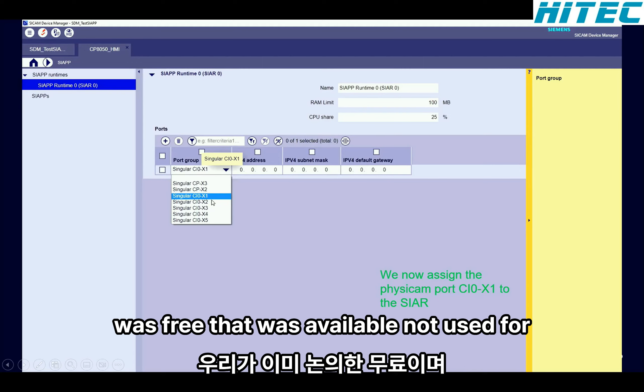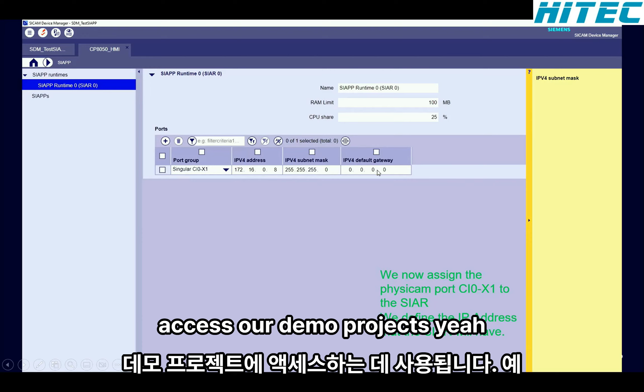I select here the port that I want to use for the SICAM application runtime, the one we already discussed that was free and available, not used for internal purposes. Perfectly, this one is fine. Then I set an IP address to this port. From now on, this port in the RTU will belong exclusively to the SICAM application runtime and will be used by any external browser to access our demo project SIAP.